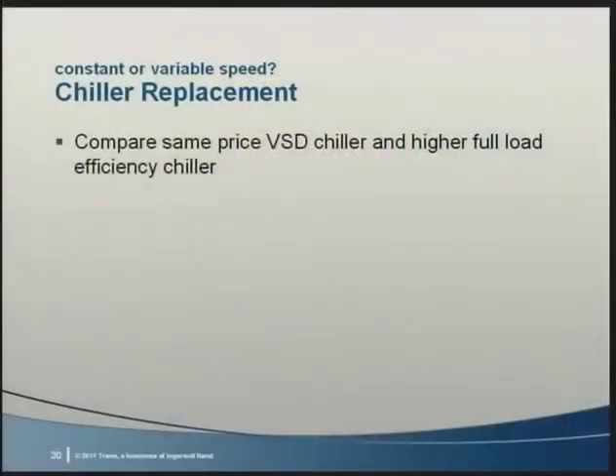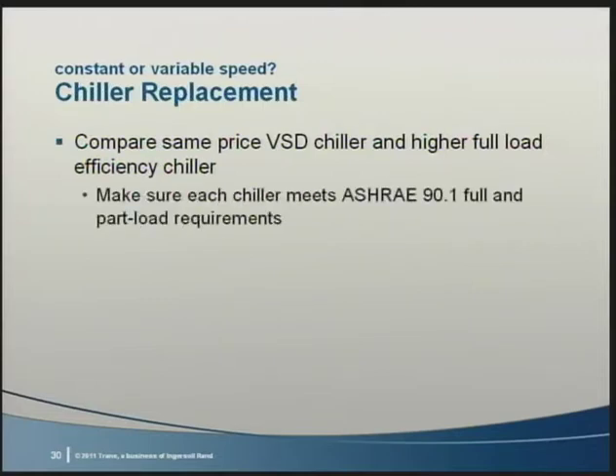Why wouldn't it necessarily be the right option when replacing a chiller? In a retrofit using the existing chiller, a VSD is likely to improve the performance more than any other upgrade, especially if controls are also upgraded at that time. But when we're replacing a chiller, a VSD is just one option. We ought to consider investing in a constant speed chiller at the same price with a higher full load efficiency. In either case, make sure the new chiller meets both the full and part load requirements of 90.1.